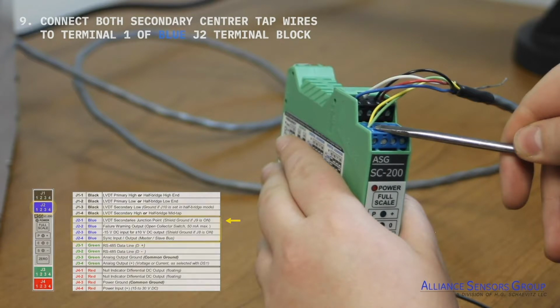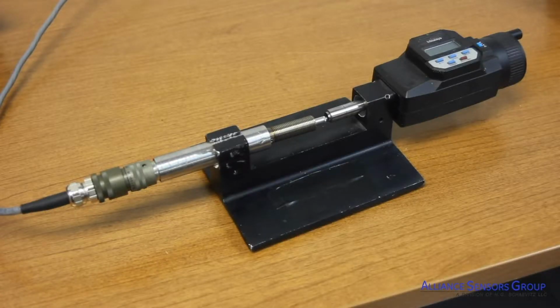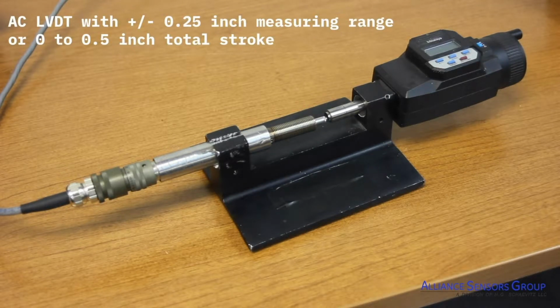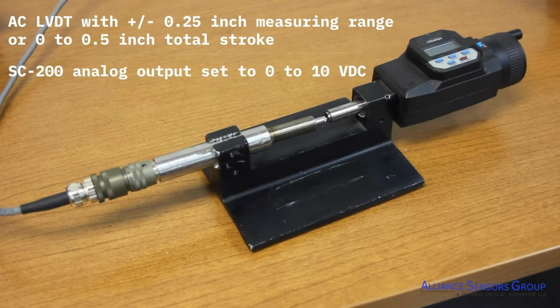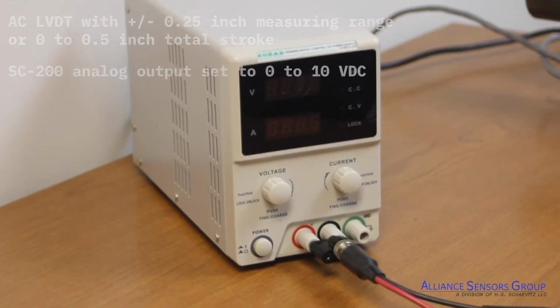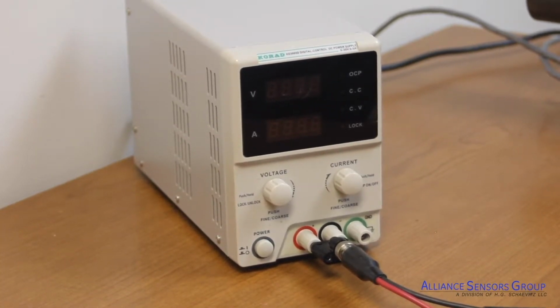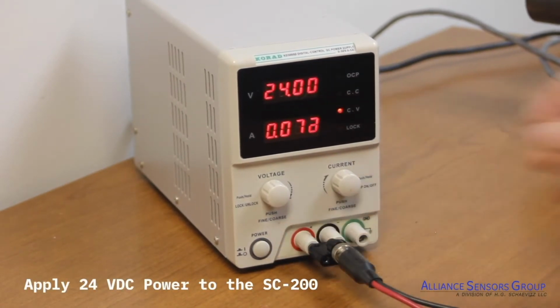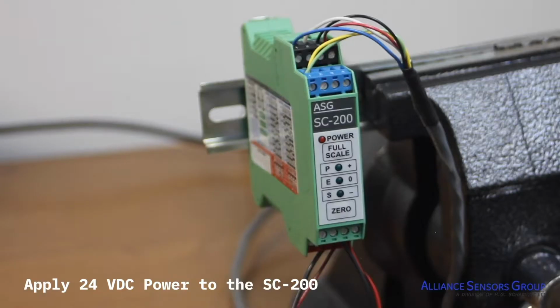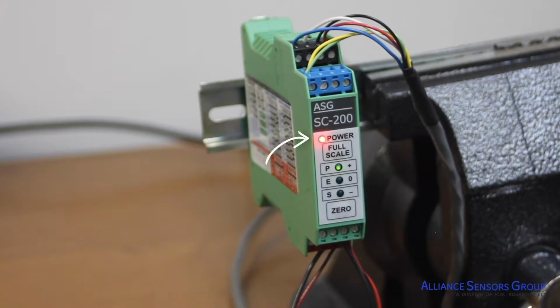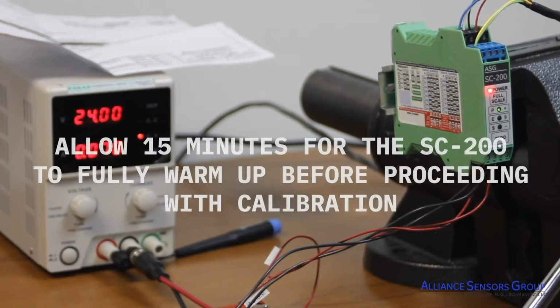For this demonstration, we'll be using an AC LVDT with a plus and minus 0.25 inch measuring range, or a 0 to 0.5 inch total stroke, and the SC-200 analog output setting set at 0 to 10 volts output. Now, with all the connections made and the LVDT positioned into the test fixture, we will apply 24 VDC power to the SC-200. The red power LED on the face of the unit will illuminate, indicating power is present. The green P LED will illuminate as well, indicating that the SC-200 is operating as a master. It's important to allow 15 minutes for the SC-200 to fully warm up before proceeding with calibration.